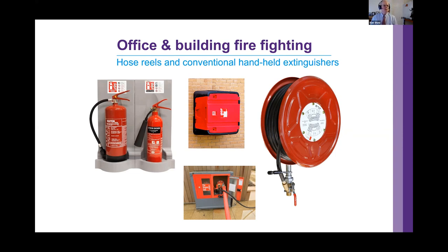They connect the fighting hose within the building to those hose outlets on upper floors. If the building is higher than 18 metres or more, pipework is usually left filled with water, and that is then known as a wet riser — that's much quicker to operate. It needs inspecting and testing. Both systems need to be tested annually so that their pressure is affirmed. Wet risers often save time because you don't need to fill the dry riser.